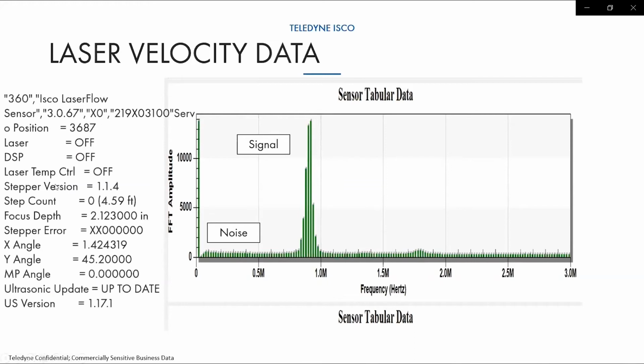Some additional diagnostics are built into the system. It tells me the step count, how far the laser is transmitting away from the water, and the focus depth, how far it's going below the water. I can see my X and Y angle, that it's still level. X should be 0 plus or minus 3, Y is 45 plus or minus 3 degrees. So I know everything is still good in this application.